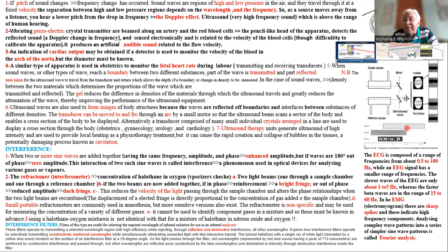Of course, this instrument is non-specific. What's the meaning of that? It can be used to analyze any other vapor. The second thing, it cannot identify a mixture of vapors. But if I know preliminarily what the components of the mixture are, I can evaluate the concentration of each. So these are the points I must take into consideration when I use the refractometer. Of course, nowadays there are portable apparatus. At first, they were difficult to calibrate. Nowadays they are as accurate as the bigger one.